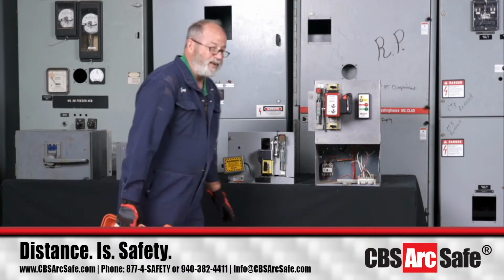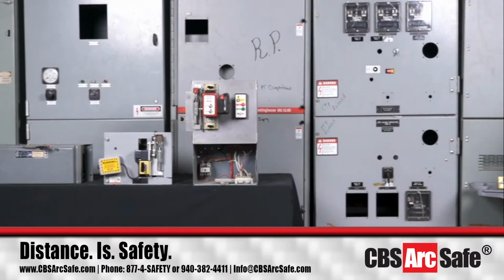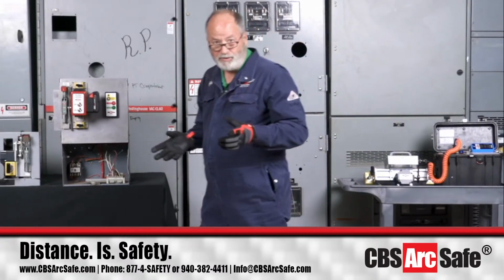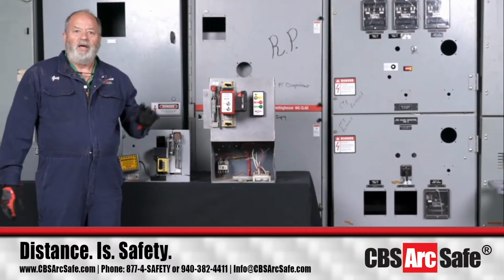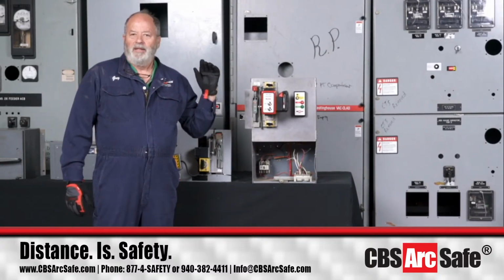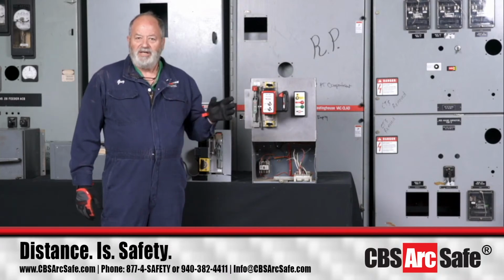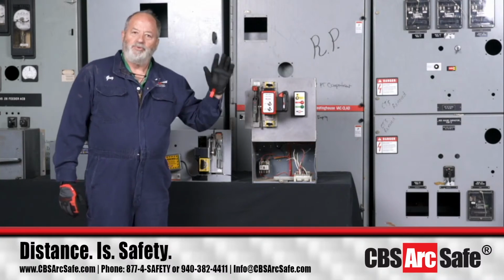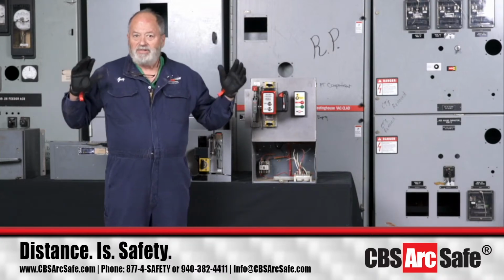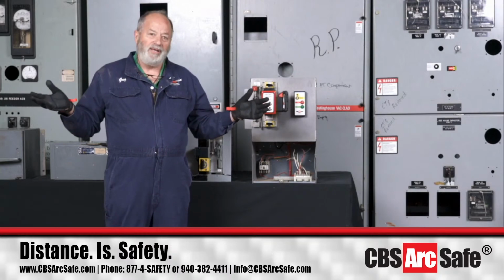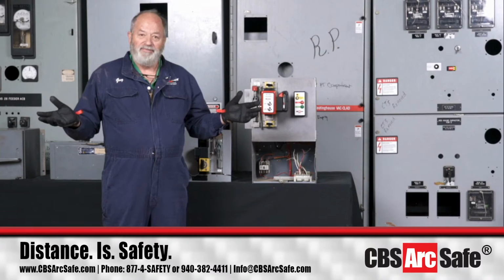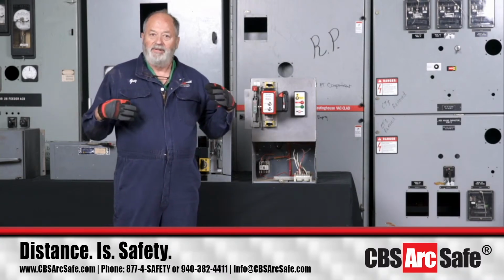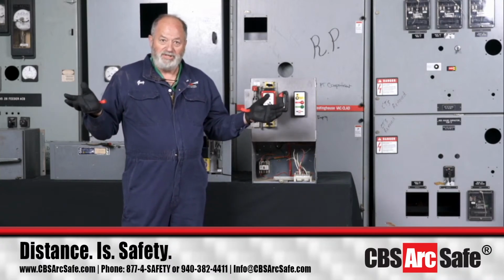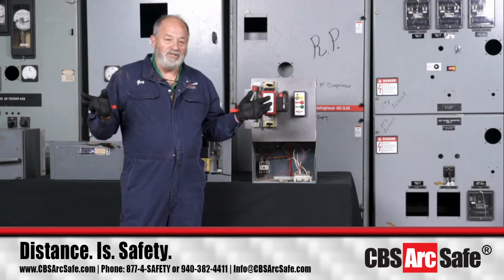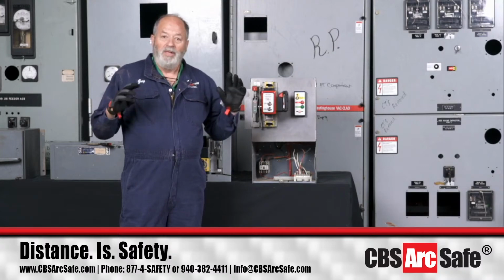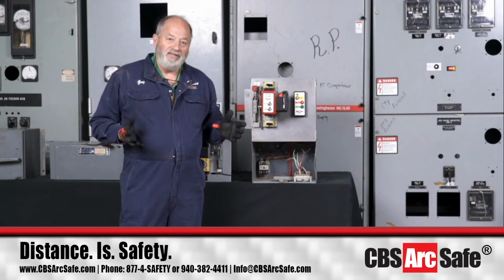One of the other products I'll talk about briefly, though you won't see it today, is the RS2 bucket extractor. Even though we're not demonstrating it, lots of facilities need these, especially if you've got a 5 kV transformer feeding just an MCC without a 480 main breaker upstream to protect it. You may have an entire room with exceedingly high, over category 4, arc flash hazard boundaries. The first time I ran into that was about 11 years ago at a refinery in Louisiana, where they would have had to shut down to do one MCC bucket change because of the way the place was wired. So even though we don't have it today, if you have something like that, please give us a call.